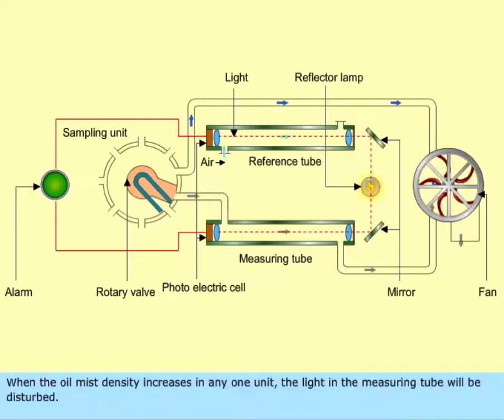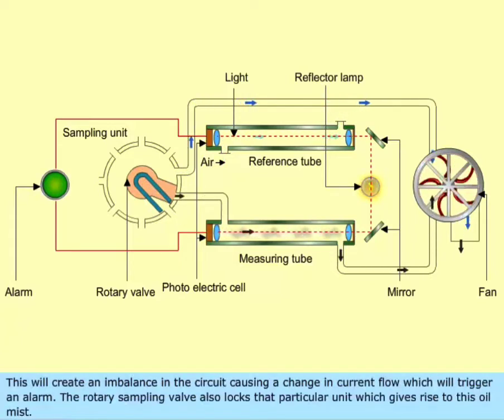When the oil mist density increases in any one unit, the light in the measuring tube will be disturbed. This will create an imbalance in the circuit, causing a change in current flow, which will trigger an alarm. The rotary sampling valve also locks that particular unit which gives rise to this oil mist.